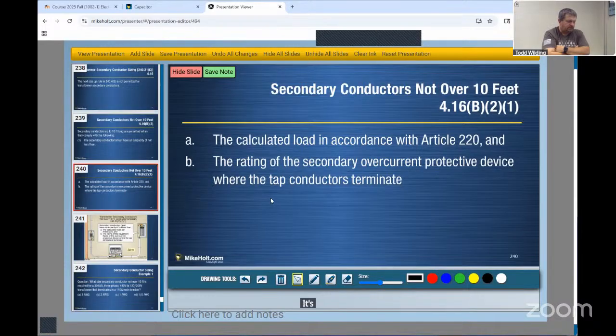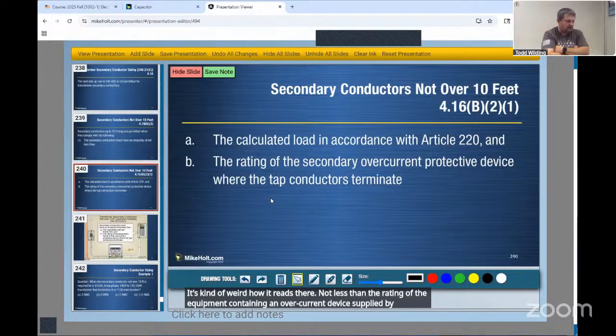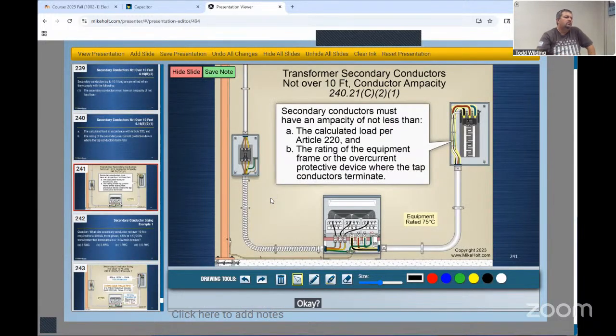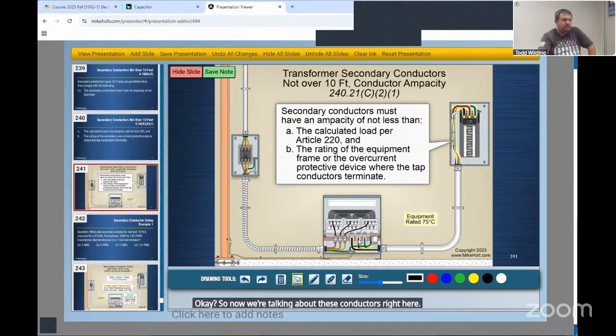It's kind of weird how it reads there. Not less than the rating of the equipment containing an overcurrent device supplied by the secondary conductors, or not less than the rating of the overcurrent protection device at the termination of the secondary conductors. Okay. So now we're talking about these conductors right here, coming off the transformer secondary up and into this overcurrent device. Not over 10 foot long, which is typical. You'll see that quite a bit.